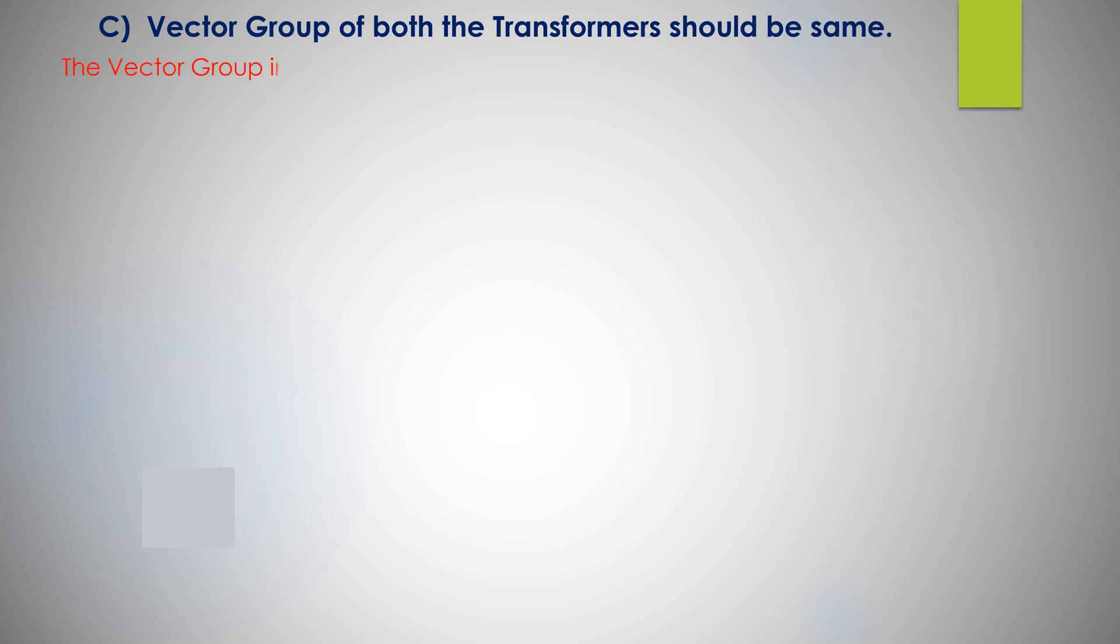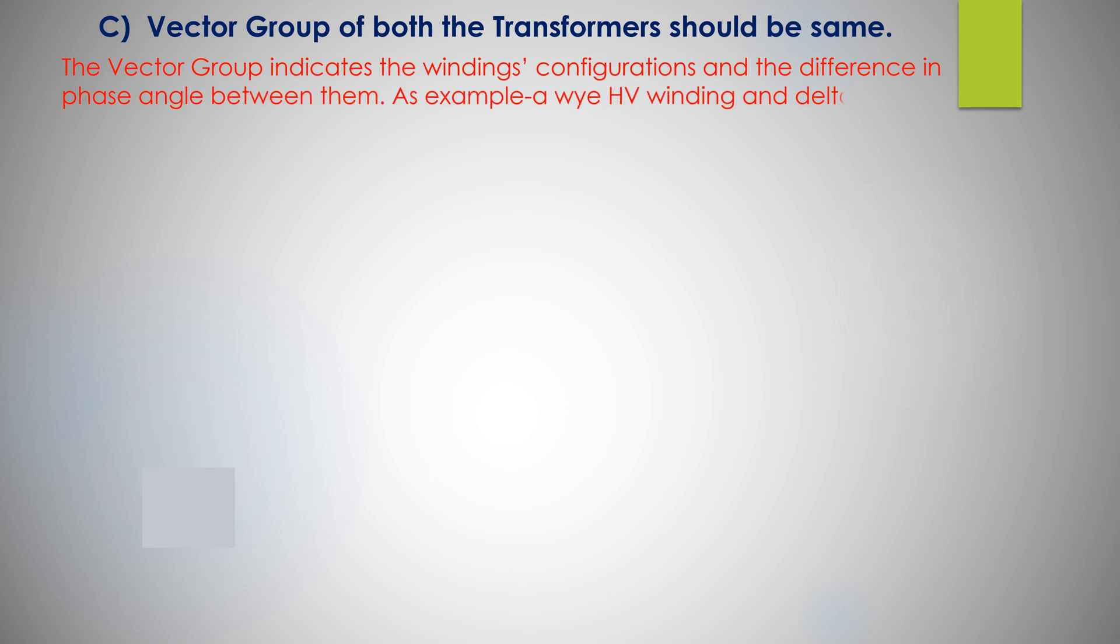Vector group of both transformers should be same. The vector group indicates the winding configuration and the difference in phase angle between them. For example, a Y HV winding and delta LV winding with a 30 degree lead denoted as YD11.